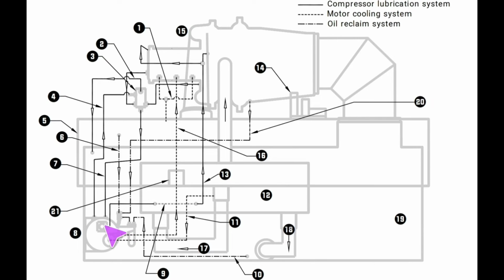So what it is doing is you come out the regulator through a cooler inside the economizer. So this cooler inside the economizer is exactly that, right? It helps make sure the oil maintains a proper temperature going into the compressor. It's why it's also important that we maintain a proper oil temperature inside the sump, so that in any additional cooling that needs to happen, we've got the proper temperatures in order to get the right oil temperature to the compressor. So then we come out here and we kind of tee off into two lines.